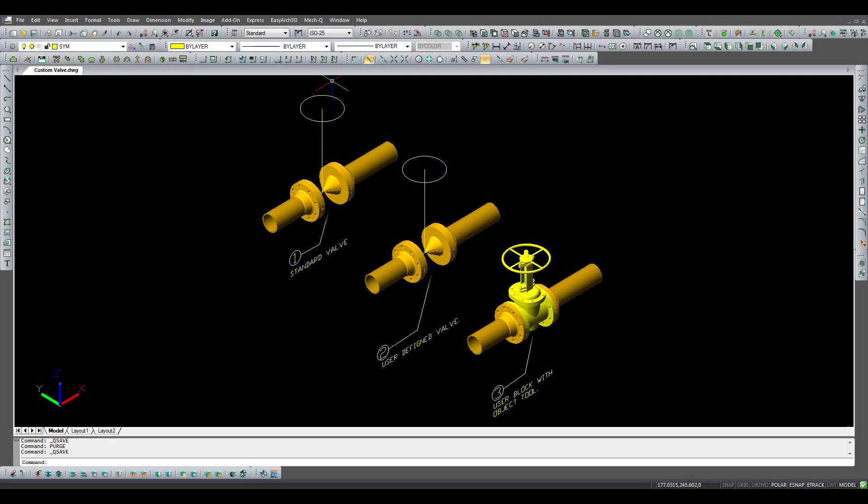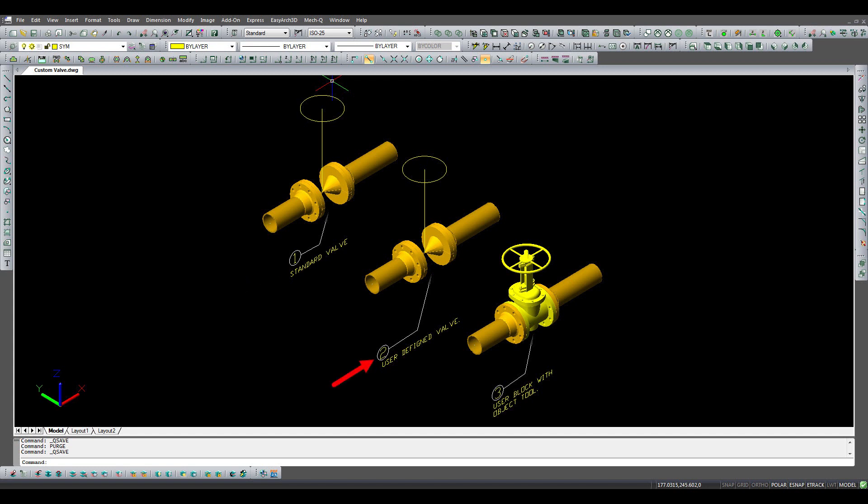Here you can see we have three flange valves. The valve labeled number one was installed using the standard valve dialog box. The valve length and handle height were adjusted before the valve was inserted. The valve labeled number two was installed using the user-defined valve dialog box. The dimensions for this valve were added automatically from the database file. The valve labeled number three was a custom-built block made using the basic solids modeling tools found in most CAD engines and Mech-Q's mechanical detailing tools. This valve was marked as an object using the object option in the Mech-Q piping dialog box.